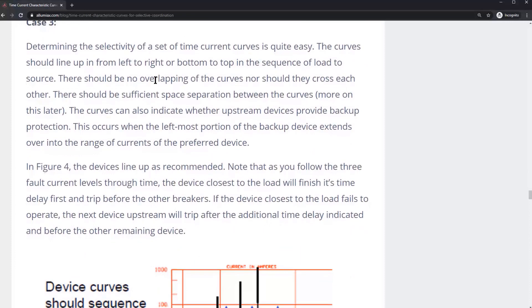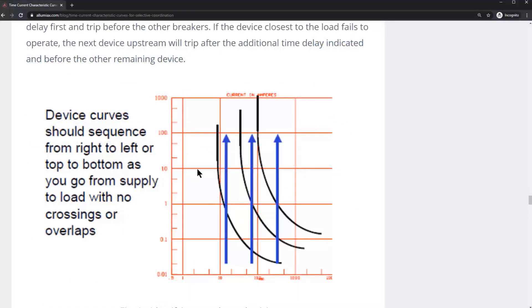Determining the selectivity of a set of current curves is quite easy. From load to source, the curves should be stacking up.